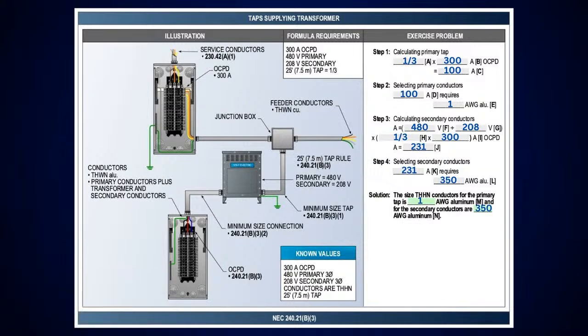And if I go over and pick up my conductors, this one we're actually doing aluminum. We pick up our aluminum size conductor, you need at least a 350 kcmil conductor for that secondary. Okay. I think what Juan is talking about is the tap ratio is 33%. Yeah, the tap is 33%. That's the ratio they put on there.